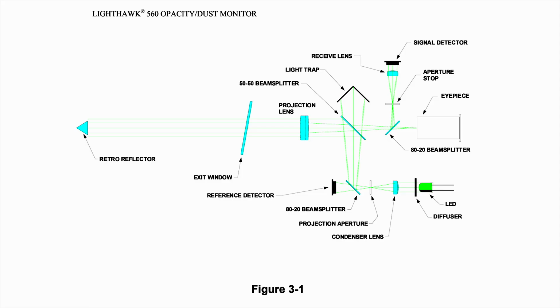The LightHawk 560 is a double-pass system design. An LED light beam is projected through the sample path, and the optical head measures the attenuation of the amount of light returning from the reflector. The opacity is equal to 100% less the percent transmission, i.e., 80% transmission equals 20% opacity.